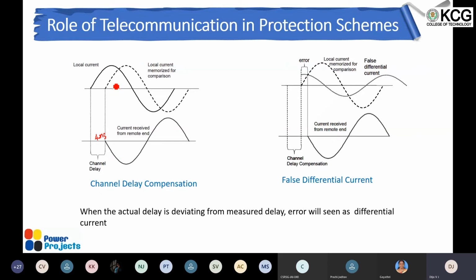Okay, so the scheme looks good with this, but in case there is an issue in the communication channel and there is a longer time delay, what could happen? We have taken the channel time delay for comparison as 4 millisecond, but in reality it was slightly more, probably 5 millisecond or something. Because of some issue, maybe a device came in between in the communication network, maybe a kind of attenuator or some other device, without the knowledge of the protection engineer. Generally in any substation or any industrial system, there will be a protection department for the protection relays, and a separate telecom department for laying the optic fiber cable and other telecommunication equipment.